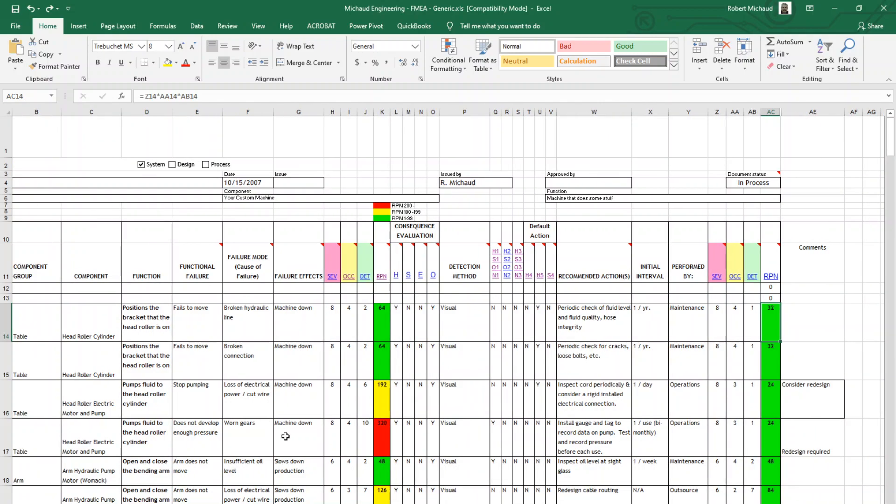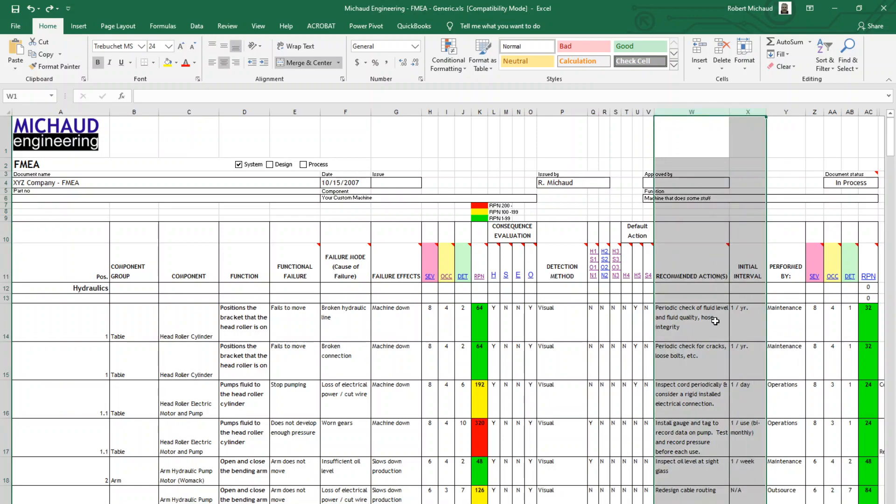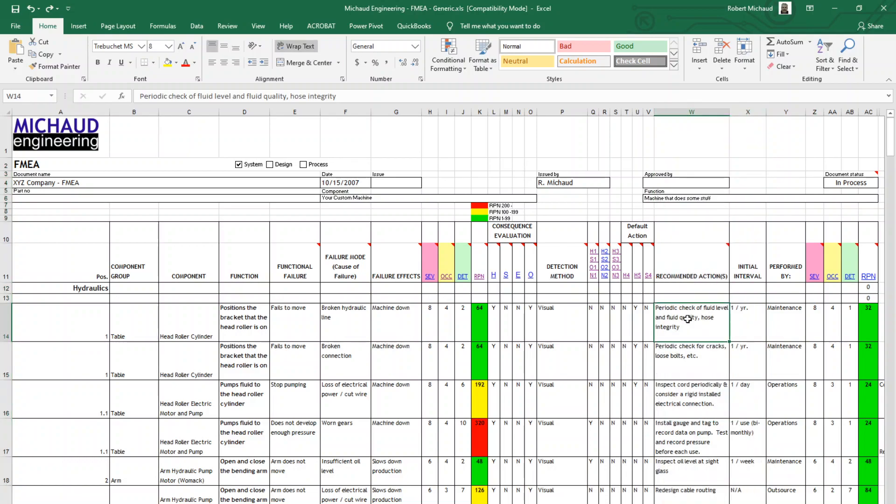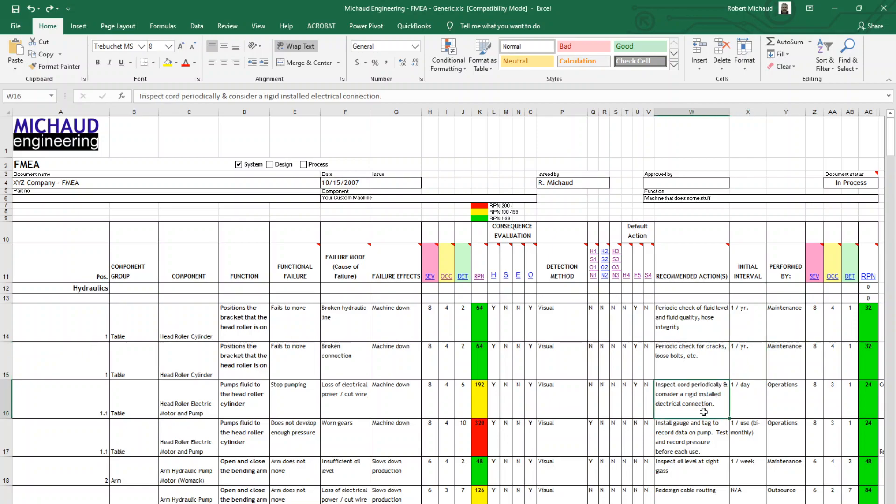Also, once the entire machine has been evaluated, your PM tasks are basically these two columns. You're going to create PM work orders for each of these items on these frequencies. And these PM work orders will go into your existing CMMS or asset management system. Or if you don't have a computerized maintenance management system, they would go into a paper-based PM program. But I highly recommend looking into a CMMS if you don't have one already, because it gives you tools to go back and review the performance of your maintenance efforts in the future a lot more easily.